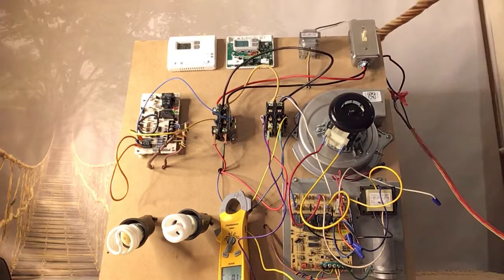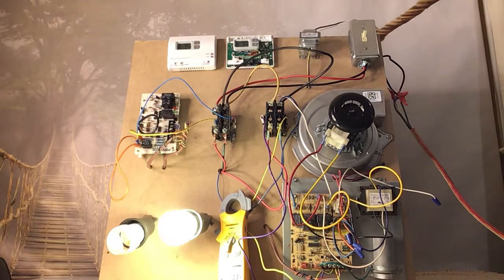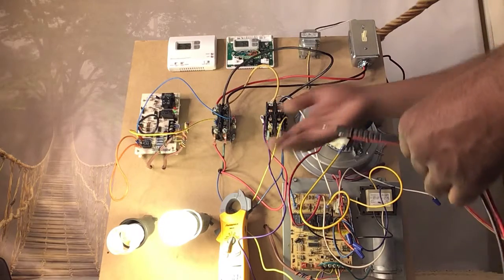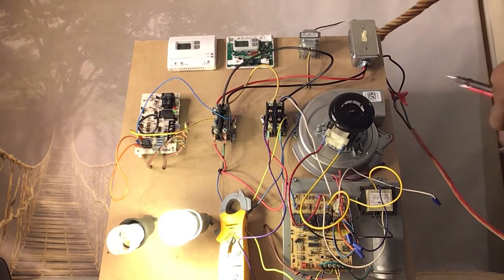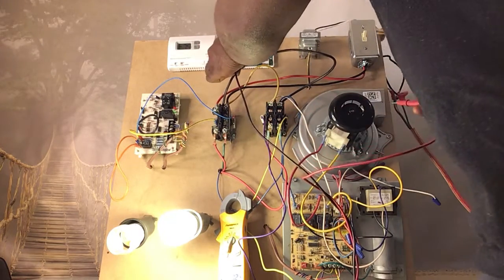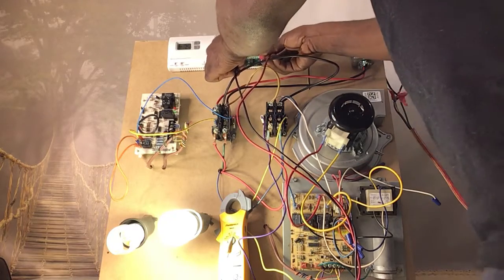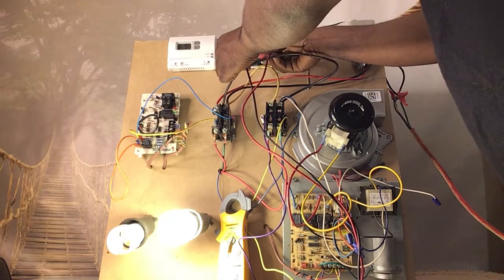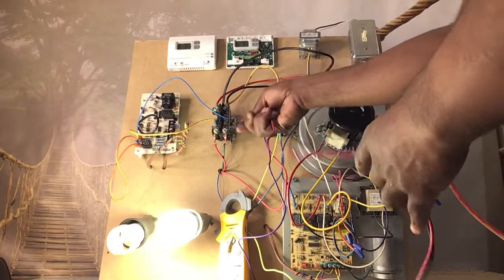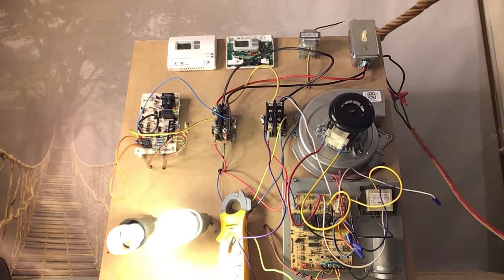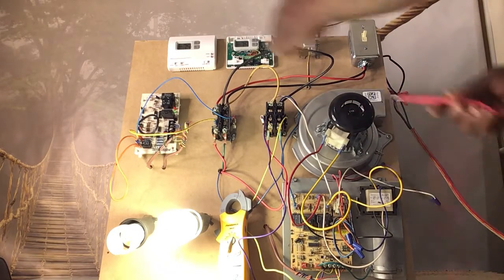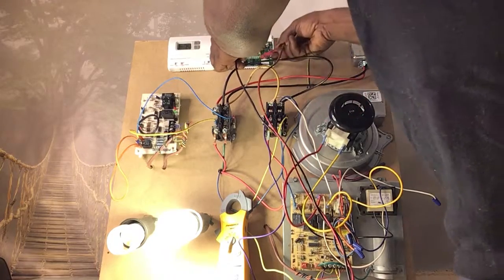We're going to watch it run through the cycle. Remember that the thermostat has a delay on it, so give it some time to show up. So now that our system is actually running, or our light is on, if we check from common to yellow, we got 24 volts. This is what actually just pulled in our contactor. So we have no faults nowhere. Common to yellow is how you check to see if your unit has a call on it.